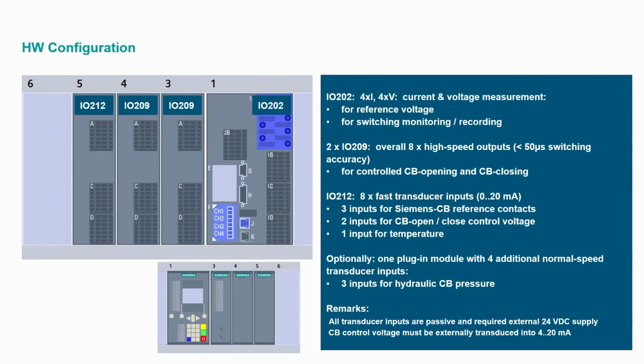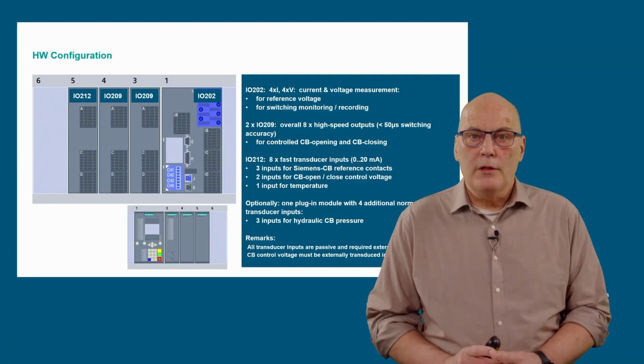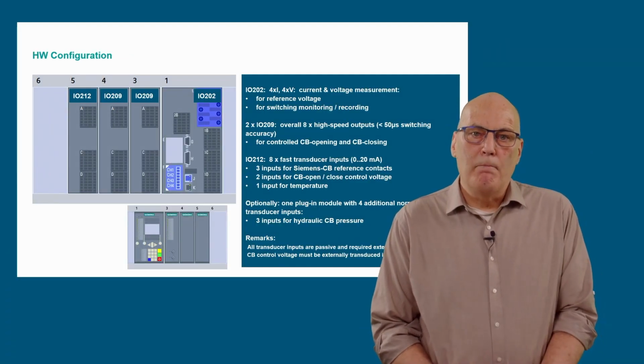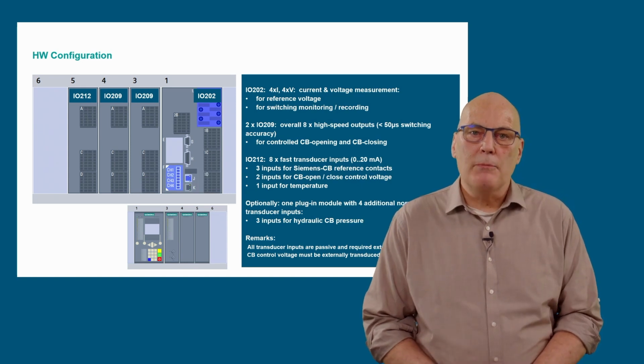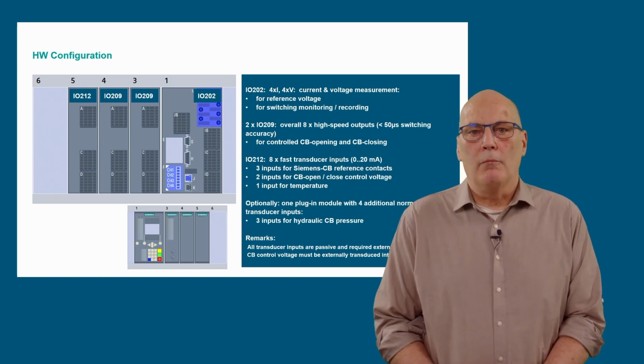The hardware configuration of the device may now be done. For the point-on-wave function, the following must be considered. Voltage and current measuring inputs for the reference voltage as well as load side current and or voltage. High-speed contacts in IO209 modules for point-on-wave switching commands. All switching commands by point-on-wave must be via such a high-speed contact in the IO209 module.